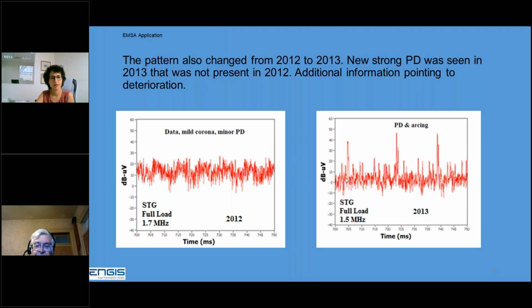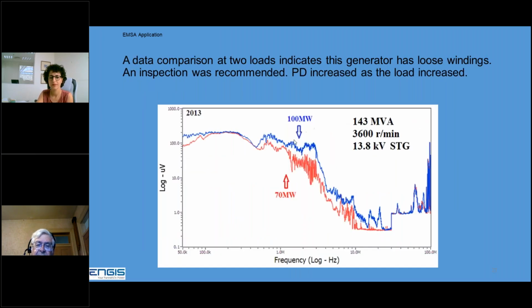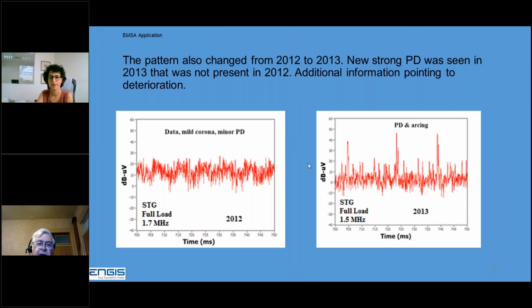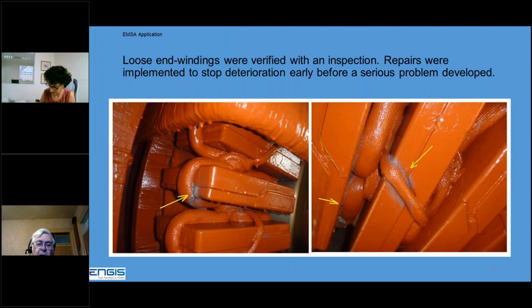The next year, we get some very tall partial discharge spikes, and this opening down here where it's a little bit wider, that's arcing. So that change in pattern at this area indicates also that they need to plan an inspection and do some repairs. When they got into it, they found this very, very minor partial discharge activity going on, and that's good. You want to catch it very early before serious problems develop.